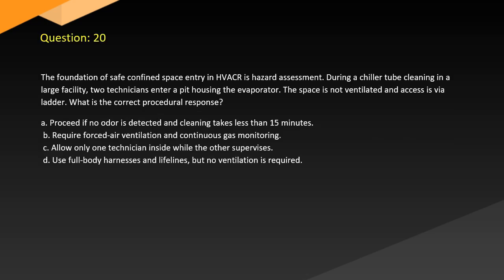Question 20. The foundation of safe confined space entry in HVACR is hazard assessment. During a chiller tube cleaning in a large facility, two technicians enter a pit housing the evaporator. The space is not ventilated and access is via ladder. What is the correct procedural response? A. Proceed if no odor is detected and cleaning takes less than 15 minutes. B. Require forced air ventilation and continuous gas monitoring. C. Allow only one technician inside while the other supervises. D. Use full body harnesses and lifelines, but no ventilation is required.